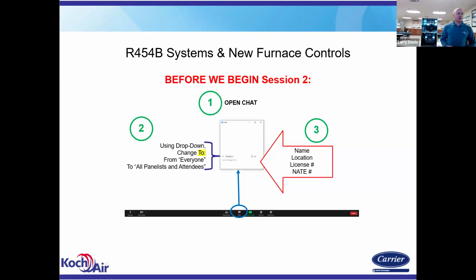One: with the SM480V gauges having a dedicated vacuum port, can you skip breaking the vacuum with nitrogen since you won't be breaking the vacuum? No. The purpose of breaking the vacuum with nitrogen multiple times, again, is to dislodge any pockets of refrigerant that may be sitting there, maybe being held in with some oil or something like that. The double vacuum and breaking it with nitrogen is required with the 454B refrigerant. You're doing a sweep of that system with the nitrogen. Okay.